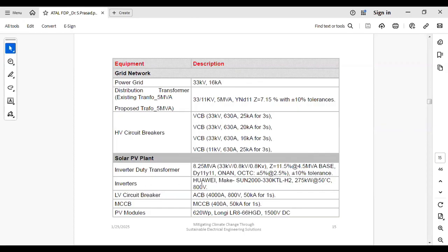And for the inverters, you can see the make and model. The other details you will get from the OEM, originally in the equipment manufacturing data sheet. The other breaker details are also important for short circuit analysis. So therefore I'm specifying here, and I'll show you the circuit also, to explain how to design a PV plant using software. I will show you the ETAP software, and how the load flow is conducted. I will show you just one single line diagram where we have conducted all the studies: load flow analysis, short circuit study, and then reactive power analysis.